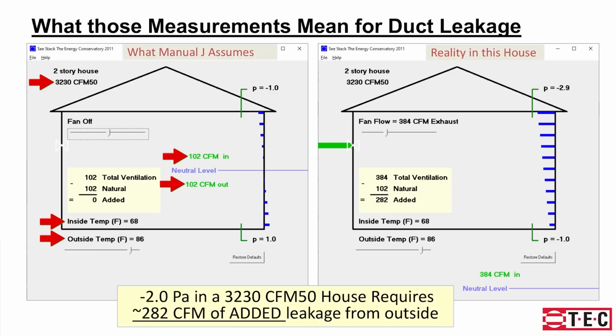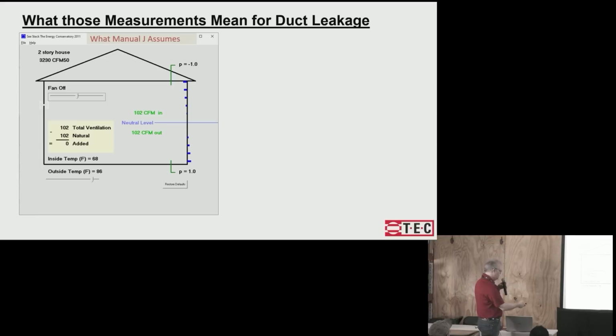It also tells us that at the bottom floor, we should expect the pressure to be about +1 pascal because of the temperature difference, and about -1 if we were to measure way up at the ceiling of the top floor. And that's pretty close to what the technician measured. The simulation tells us you should be measuring 1, technician measured 0.8. Okay, that's just from the stack effect. That's how much we should have, that's how much we've got.